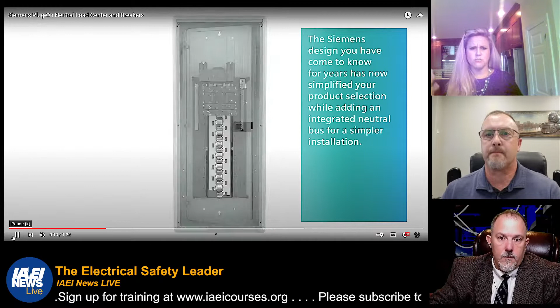This was a design to remove that pigtail. So we're running neutrals down the interior of the load center, and your breaker now plugs onto that neutral bar, which is where you get power for the electronics. Those two shiny pieces, the two lines that go straight down, are the neutral bar. The breaker has a neutral clip that plugs onto that, and a load clip that plugs onto the line side. So you've got your line power and your neutral power powering your electronics, and now you don't have all those pigtails. That's demonstrating the pigtails coming out, now replaced by plug-on neutral.